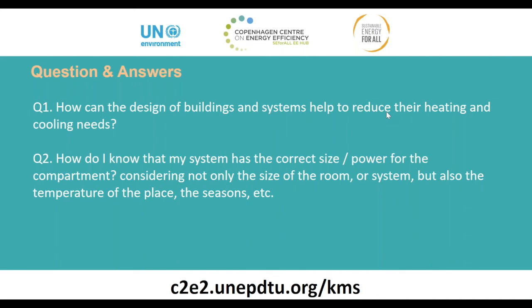If it is way too low, that means you have over-designed the systems that are installed, because they are operating in part load conditions. So that is one of the methods you can look into. Then the size of HVAC systems can also be checked through measurements of heating and cooling loads. It could be for your air conditioning units or chillers. If it is for your specific compartment or room, then you will possibly have a dedicated air conditioning unit or heating unit there, so measurements can be done as I've shown in the slides. Or it can also be through airflow or water flow measurements, in the case of fans, pumps and blowers. It is important that you have the rated design values in place and compare your measured or identified parameters.